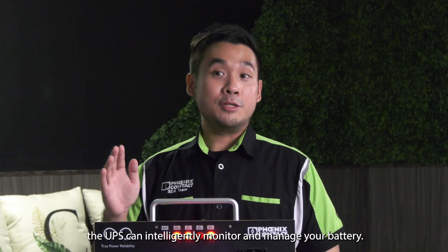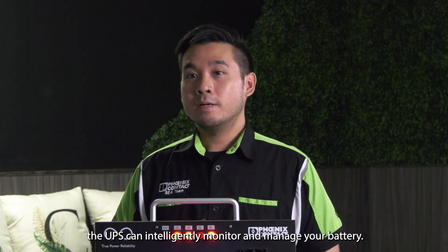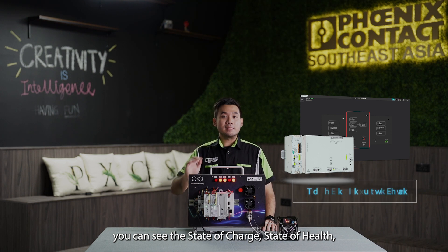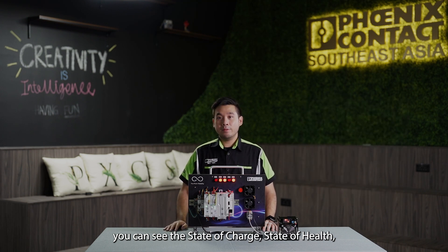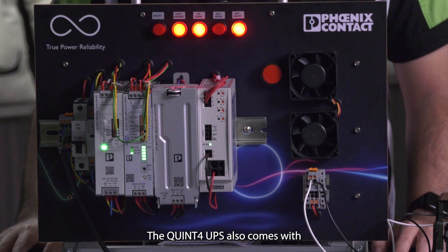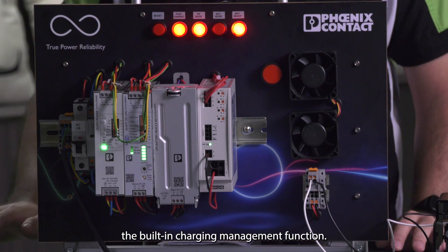During normal operation, the UPS can intelligently monitor and manage your battery. With the Power Management Suite program from Phoenix Contact, you can see the state of charge, state of health, and even the remaining lifetime of your battery, so you know when your battery must be replaced. The QUINT4 UPS also comes with a built-in charging management function.